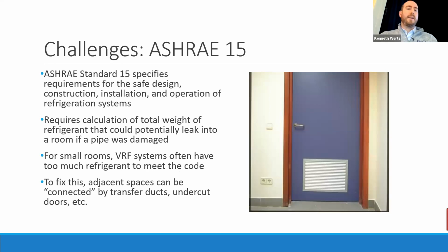I think this is the last one I had on the challenges. There's a standard called ASHRAE 15. It's part of the building codes. It basically has to do with refrigerant safety. The idea is that refrigerant is heavier than air. So if you had a leak and it got out into a space where people were, the refrigerant would displace the oxygen.